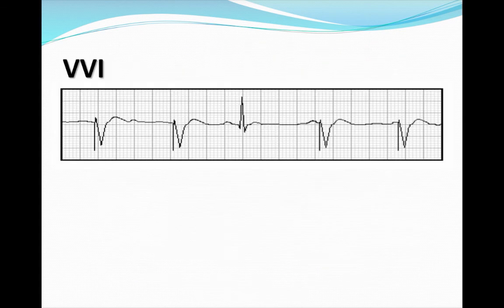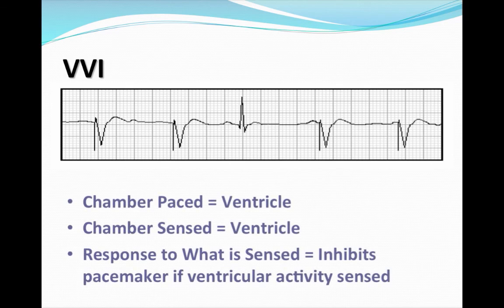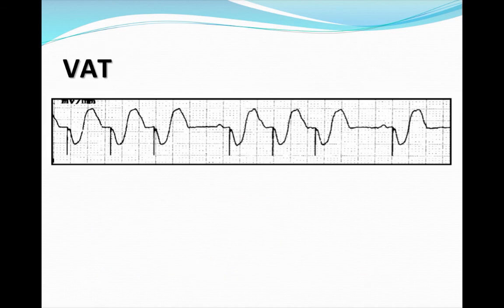Let's do some practice. VVI — the chamber being paced is the ventricle, the chamber being sensed is the ventricle, and the response is inhibit. So the pacemaker does not send an impulse when it sees the patient has their own beat. As you can see, the third beat is the patient's own beat and no pacer spike was delivered.